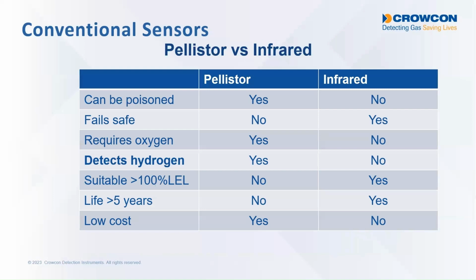So comparing the two sensor technologies, the key problem with pellistors, and it's a very real problem, is poisoning. So the pellistor bead is relying on physically coming into contact with the gas in order to detect it. If the pellistor is exposed to substances like silicone, which is a very large molecule, the silicone will coat the pellistor bead, will fill in the pores on the pellistor bead, and effectively form a coating on the bead which stops it physically coming into contact with the gas. So it then just doesn't respond to the gas.